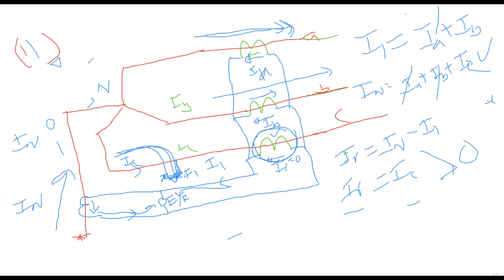But for any ground fault outside of this zone, the relay should not operate, and the relay is not operating in our consideration also. This is why this scheme is called restricted ground fault protection. It provides ground fault protection, but within a prescribed zone.